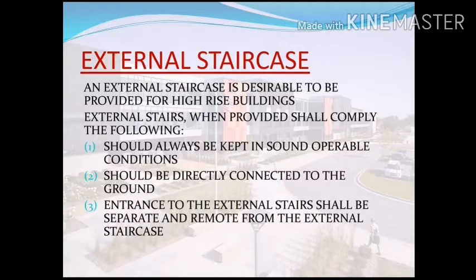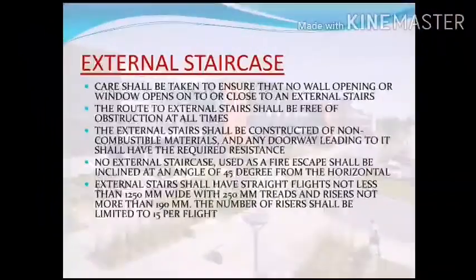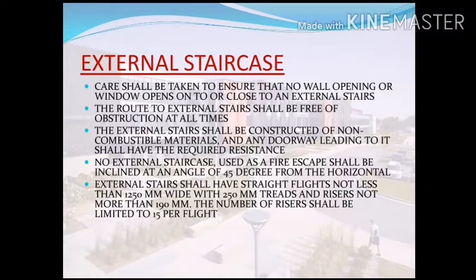All external stairs shall be directly connected to the ground. Entrance to the external stair shall be separated and remote from the internal staircases. Care shall be taken to ensure that no wall opening or window opens onto or close to the external stair. The route to the external stair shall be free of obstructions at all times.